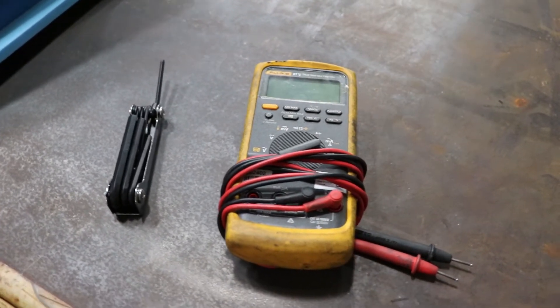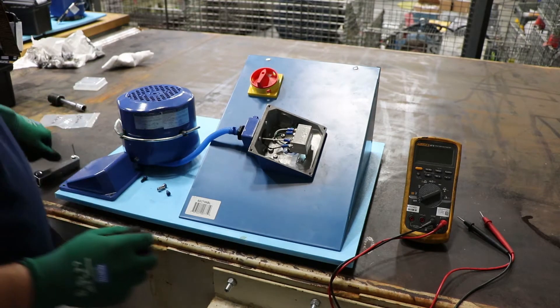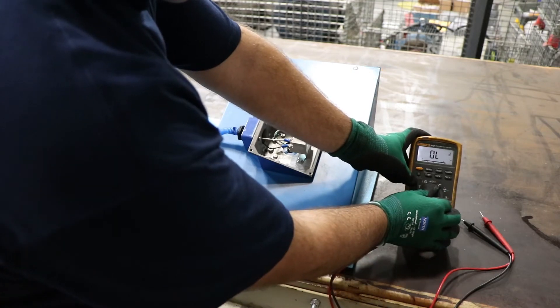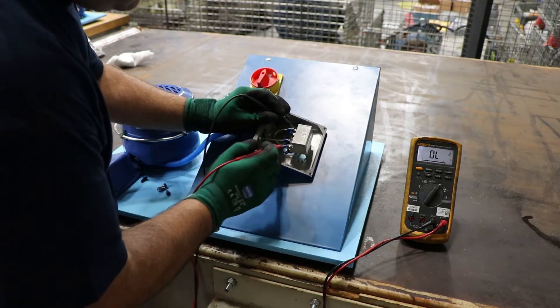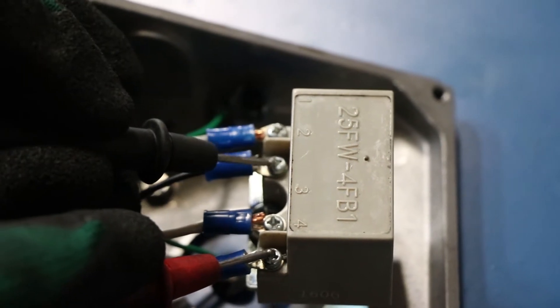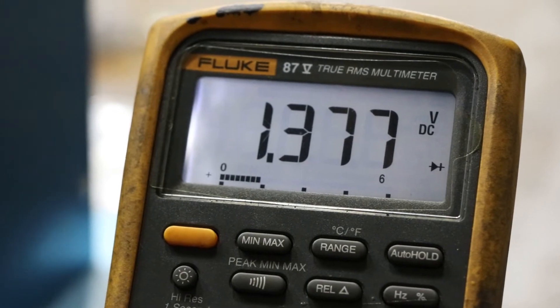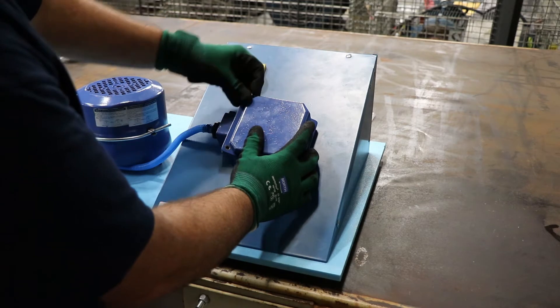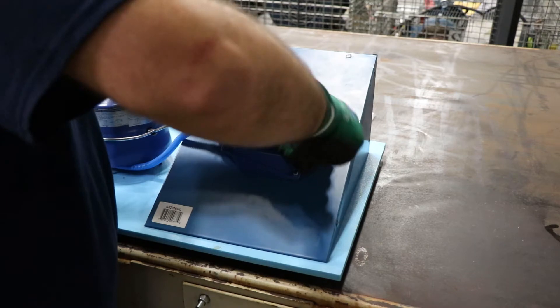First we're going to show you how to check the rectifier of one of our brake motors. All you need is a multimeter. Set the multimeter to the diode setting and with that you'll be able to make sure the rectifier is functioning properly. Check voltage between terminals 1 and 4, and 2 and 4. The value shown here might not match what you're getting, but as long as you're getting a value between both sets of terminals, your rectifier is good. If the number reads zero, the rectifier is bad and will need to be replaced.